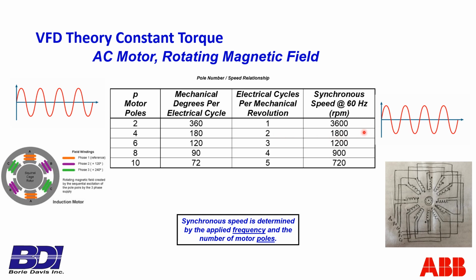Well, that's why that's a base speed 1,800 RPM motor. If there's 3,600 cycles per minute generated of the energy in the United States, and it takes two cycles to make one revolution on a four-pole motor, there you have it.